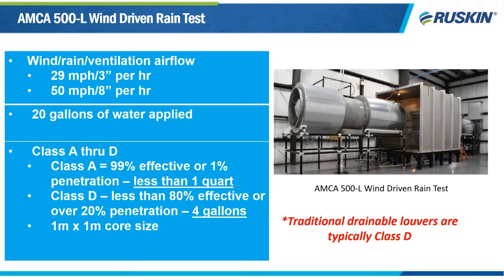As a point of reference, the standard test prescribes roughly 20 gallons of water to penetrate the open core plate in the 29 mile per hour and 3 inch per hour rain test. In that test, a class A louver allows less than 1 quart of water through it in 1 hour. In comparison, most standard louvers are class D, which allows over 4 gallons through. This is on a roughly 42 by 42 OD louver. And it's reasonable to assume that the amount of water carrying over will increase as the louver size increases. Less than 1 quart is a lot easier to manage than over 4 gallons.